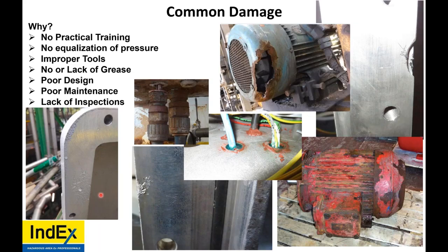Then we have other ones where it looks like pitting, old age, other things going on. A weird combination of a putty and liquid barrier glands somehow. Glands completely rusting away. And then damaged edges, perhaps from dropped covers or dropped boxes.